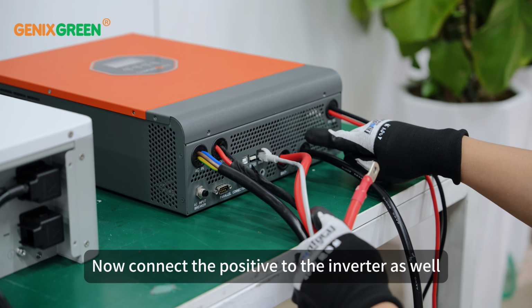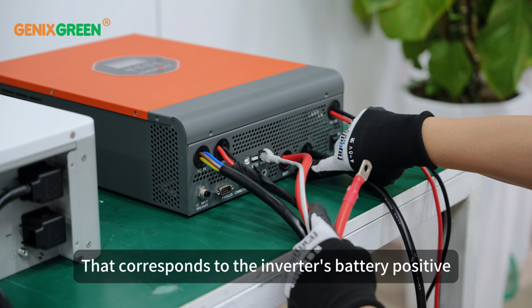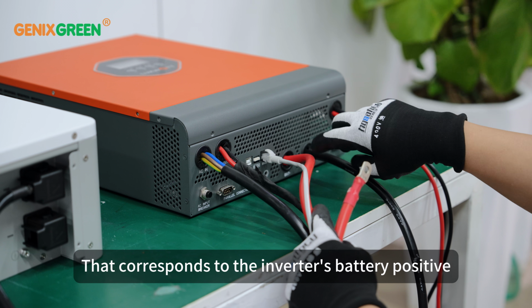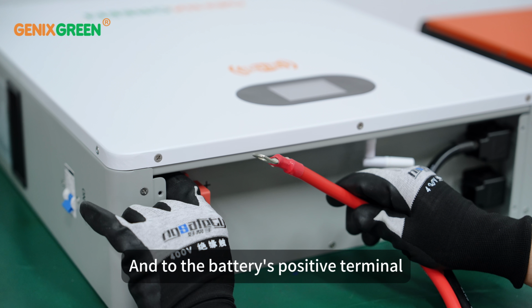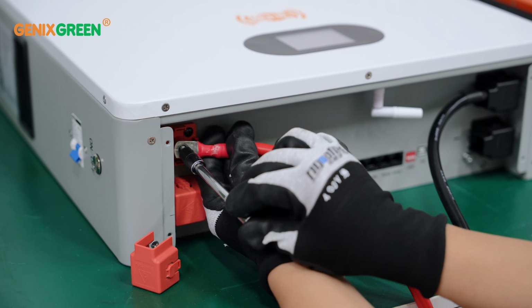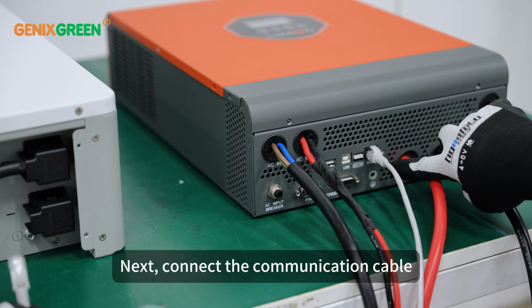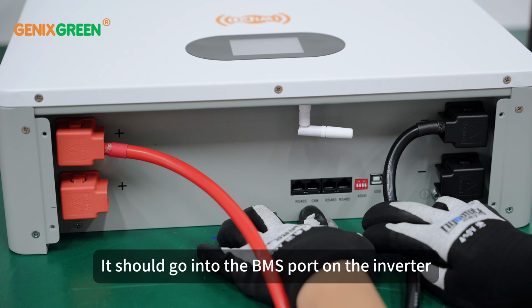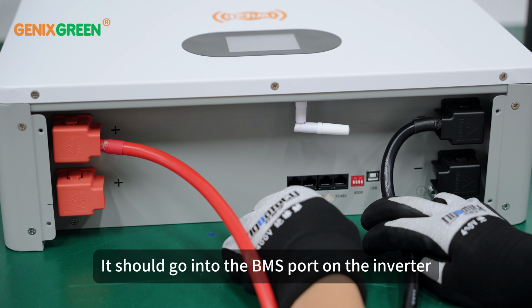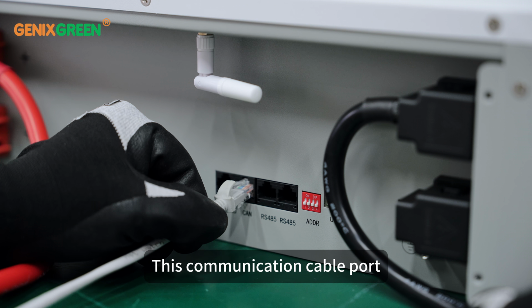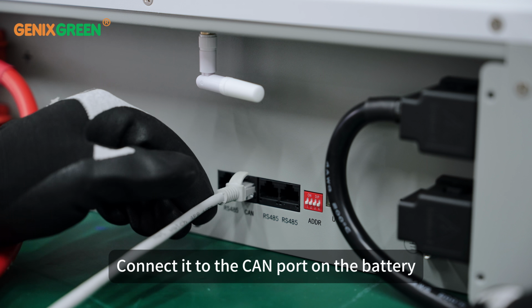Now connect the positive to the inverter as well. That corresponds to the inverter's battery positive, and to the battery's positive terminal. Next, connect the communication cable. It should go into the BMS port on the inverter. This communication cable port, connect it to the CAN port on the battery.